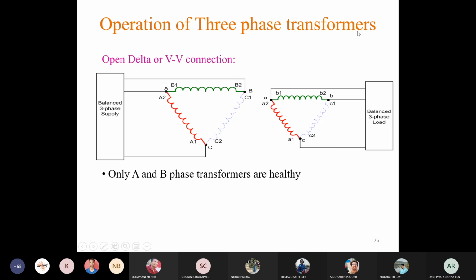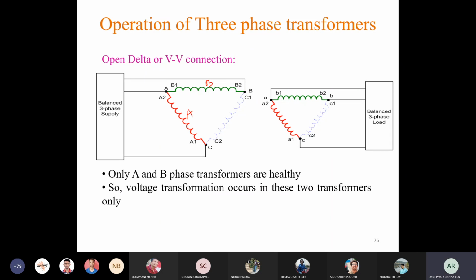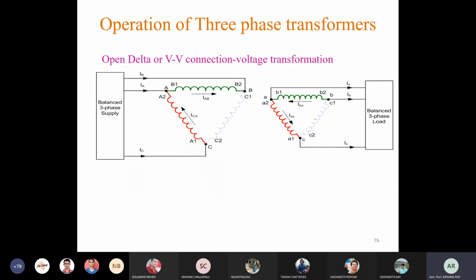Now the secondary side. Here only transformers A and B, this one and this one, are healthy transformers now. The C phase transformer is removed. So voltage transformation occurs in these two transformers only. That means the flux will be produced by this transformer and this transformer, I mean these two windings only, and those fluxes will link with these windings and there will be induced EMF. So voltage transformation occurs between these two transformers only. There is no third transformer. Okay, so how will this transformation occur? It will occur according to this ratio, that is VAB by V small ab.